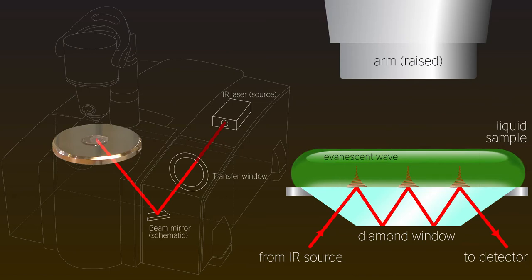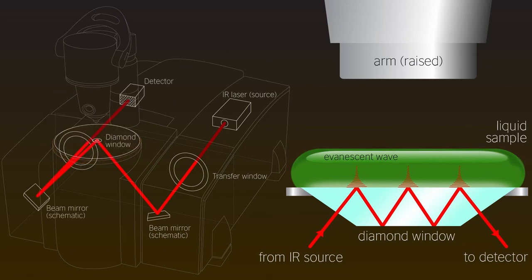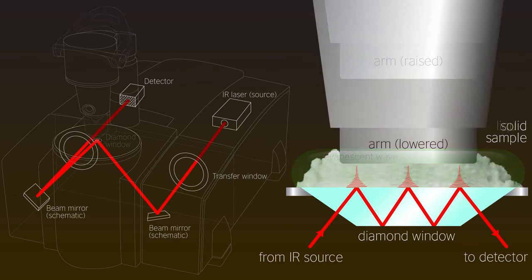As it bounces along, it interacts with the sample through an evanescent wave. It is during this interaction that the molecules of the sample are vibrated and the chemical information collected is sent along with the IR light back to the detector. Liquid samples make enough contact so that the evanescent wave penetrates deep enough to allow enough information to be collected. Solid samples, however, require the arm to push them down to ensure enough contact is made. If this doesn't happen, the spectrum will be very poor as not enough information is being sent along from the sample.